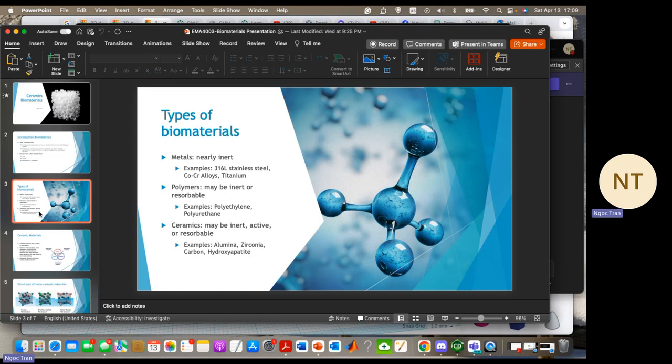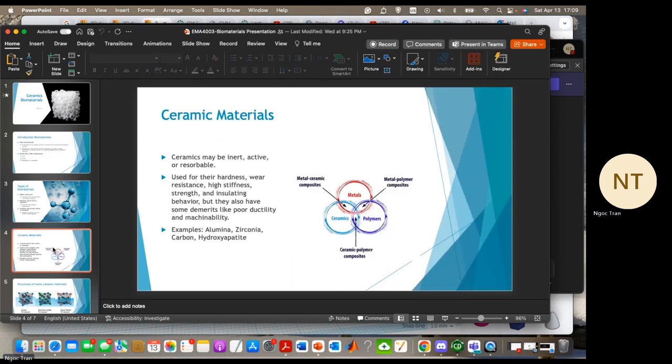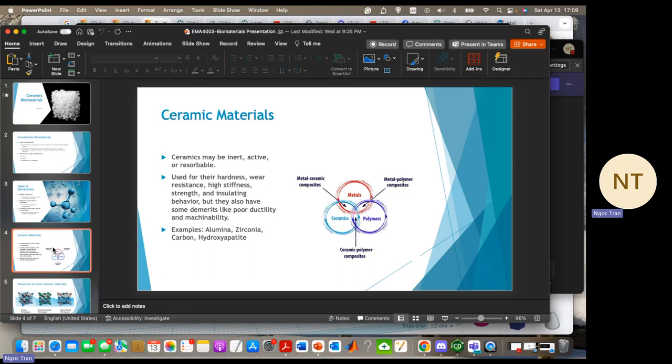And the last one is ceramic, which is the main topic of today's presentation. Ceramic materials may be inert, active, or resorbable. They're used for their hardness, wear resistance, strength, and insulating behavior, but also have some weaknesses like poor ductility, brittleness, and are very harsh to machine. Examples include alumina, zirconia, carbon, and hydroxyapatite.